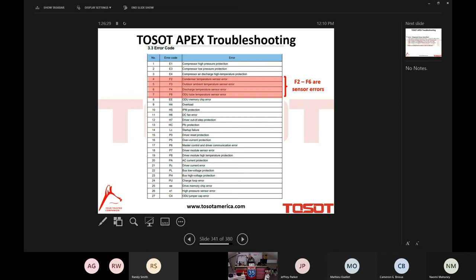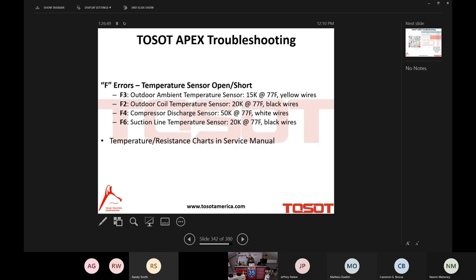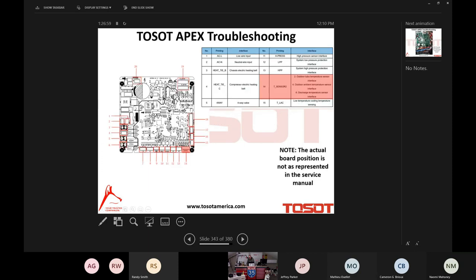So your customer will never find himself or herself in a scenario where they're potentially ohming out four different sensors to find the one in error. No. The error code will always take you exactly to the sensor that is amiss, to the sensor that is failing. Beautiful thing. And once again, we can test the resistance at each of those sensors. There are their values. We have a 15K, we have a 20, we also have a 50K as well.